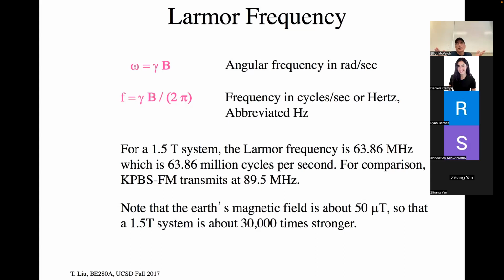So we'll irradiate, say, for 100 milliseconds, or let's say 100 microseconds, boom, with a high enough amplitude. And then you turn off your transmit, and you have a radio frequency coil by the sample. And right after you finish transmitting, you listen to the sample. The sample will irradiate back the same frequency. And this is as the protons are going through, flipping back into their steady state configuration, that flipping will happen coherently, and you will see that as a radio frequency signal.